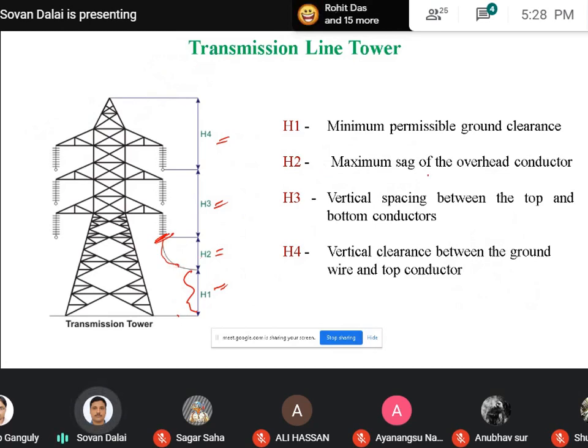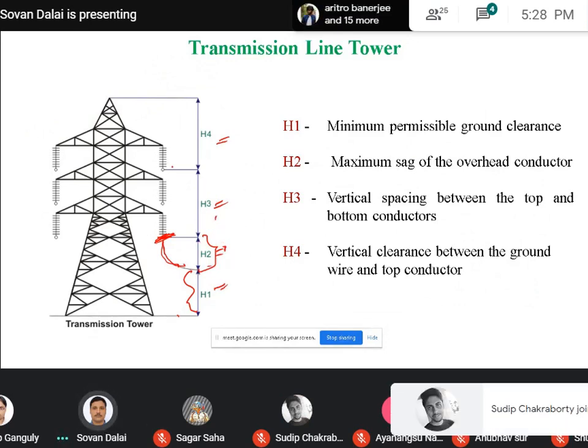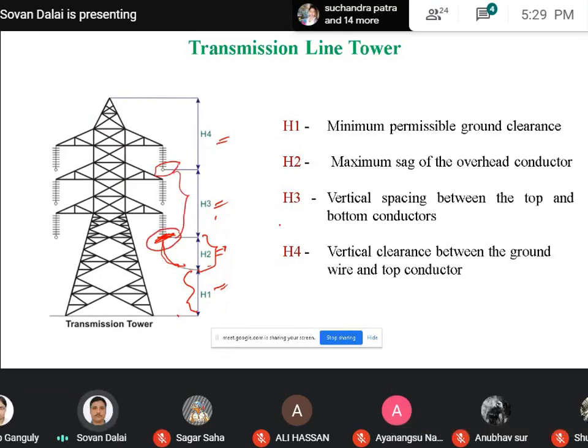H2 is the maximum sag. If the conductor is connected here, and the conductor comes to this position at maximum, that is called the maximum sag of the overhead conductor. H3 is the vertical spacing between the top conductor and the bottom conductor. In between that distance is called H3. And what is H4? H4 is the vertical clearance between the ground wire, where the ground wire is connected, and the top conductor. This is the place between the top conductor and the ground wire.